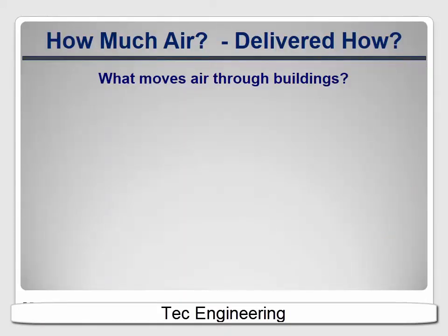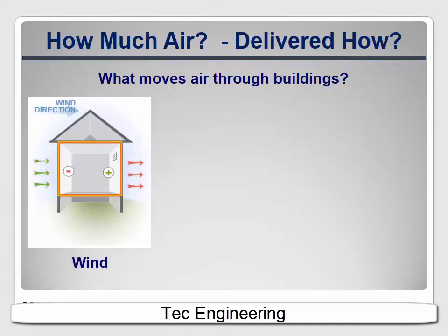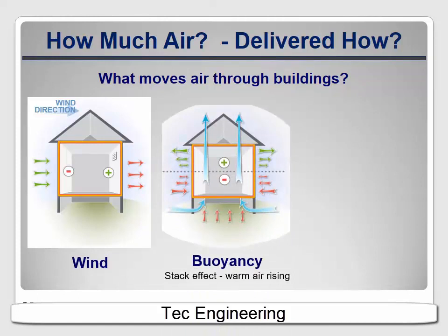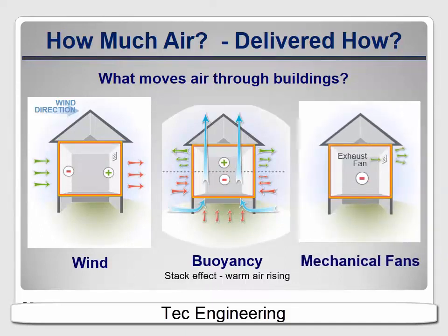To appreciate why mechanical ventilation is important, it's helpful to understand the different forces that push and pull air through houses. An obvious one is wind — wind is moving air, so of course it will find its way in through leaks. Another is the buoyancy of warm air. Warm air is light, so it rises. When it's warm inside and cold outside, the house acts like a big chimney, with the warm air rising out of holes at the top. And another is mechanical fans, which can push air out or pull it into a house. Mechanical fans are the most controllable of the three, and we can use them to ensure adequate airflow. Let's take a closer look at the other two to understand why they aren't as reliable.